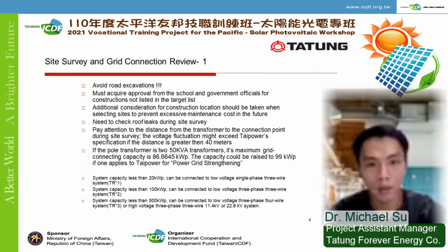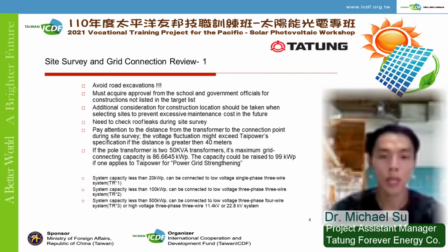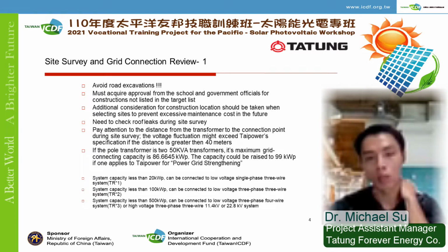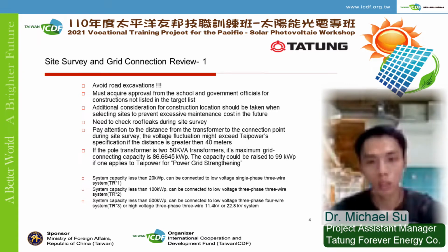Now, down here, you can see some basic rules we have in Taiwan. If the system's capacity is lower than 20 kilowatts, it can be connected to a 3-wire single-phase transformer. If the capacity is lower than 100 kilowatts, it can be connected to 2 3-wire 3-phase transformers. If the capacity is lower than 500 kilowatts, we can connect to three 4-wire, three-phase transformers, or other equipment which can handle higher voltage.